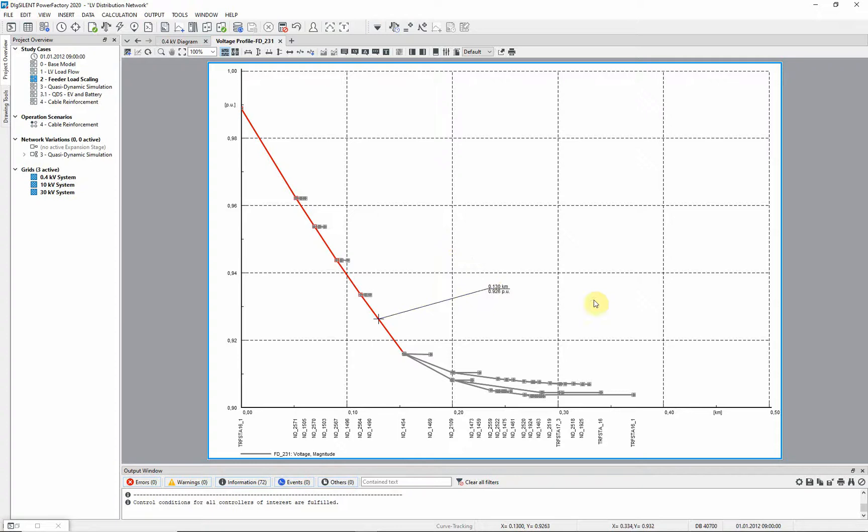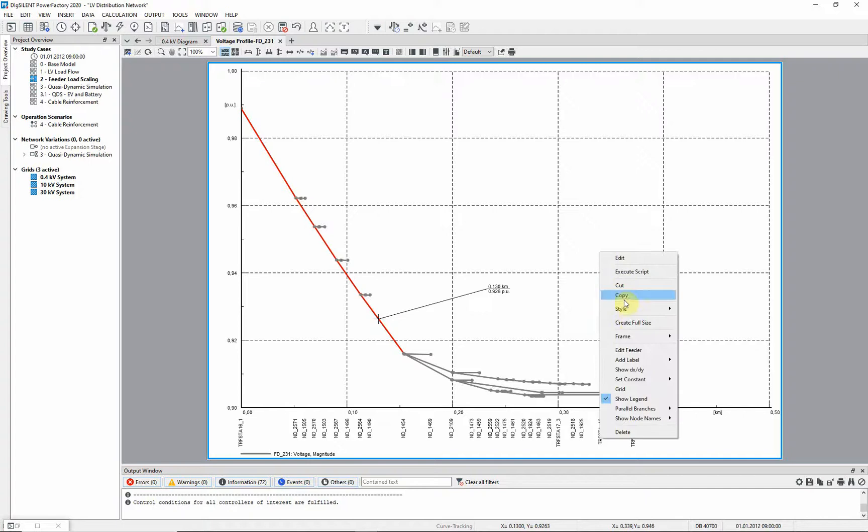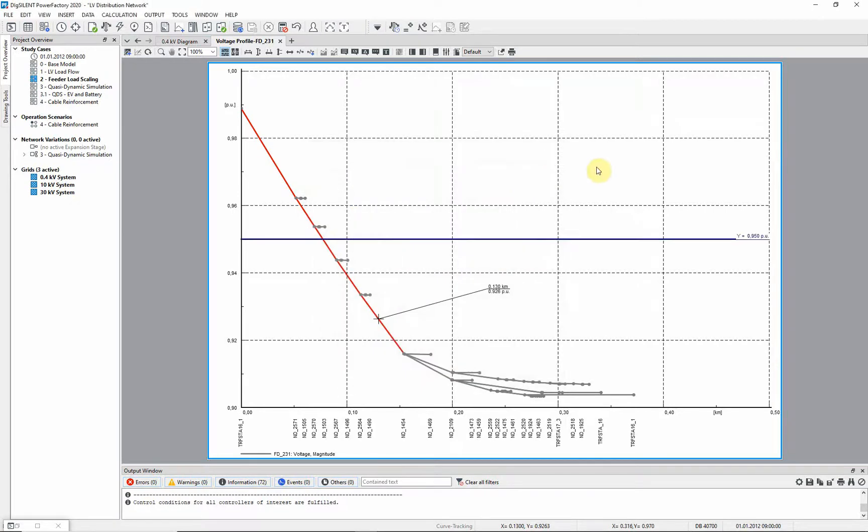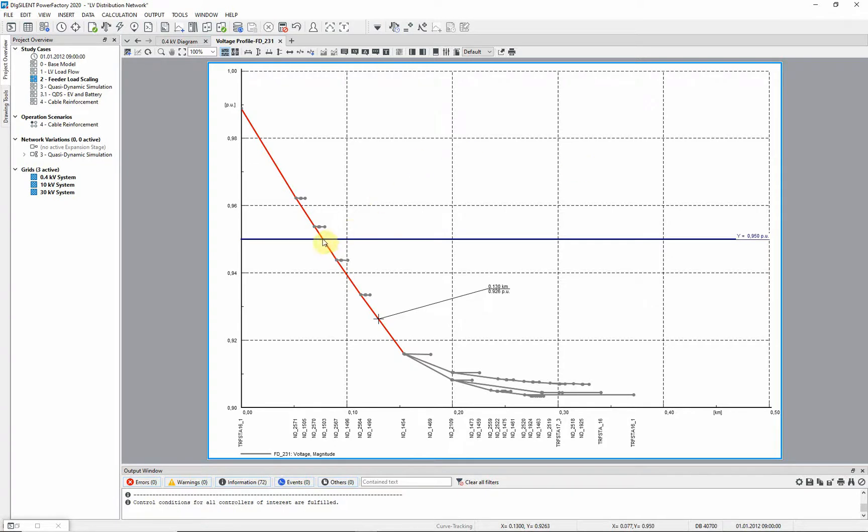We can also add a constant y-value to the curve. Right click in the graphic in an empty space and select Set Constant, y-value. We will set the value to 0.95. As you can see, the voltage in this feeder drops below the 0.95 value at some point along its length. Add a label to determine this point.